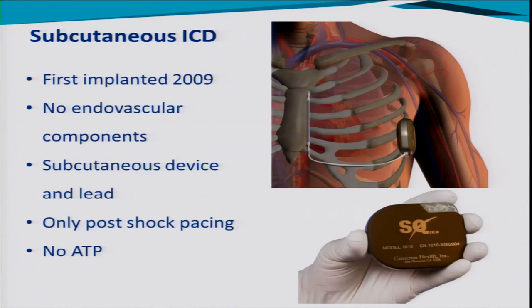Many problems with ICDs arise from leads within the vascular system, and with this in mind a new entirely subcutaneous device was developed in 2009. The device sits on the left lateral chest wall and the lead doesn't go into the veins at all — it's entirely subcutaneous and picks up a surface ECG. This is much better for the paediatric population who are growing and will outgrow their leads and device over time. The only thing to bear in mind is that it cannot pace the heart — it will only deliver percutaneous post-shock pacing, so you cannot use ATP in these devices.